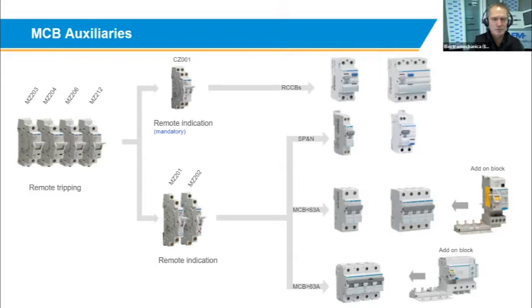You can also have a remote indication. So remote indication is just a normally open, close auxiliary contact to give you a signal whether the breaker is on or off, if you want to put it into your automation system, or an indication light on the panel to see if the product has been tripped.